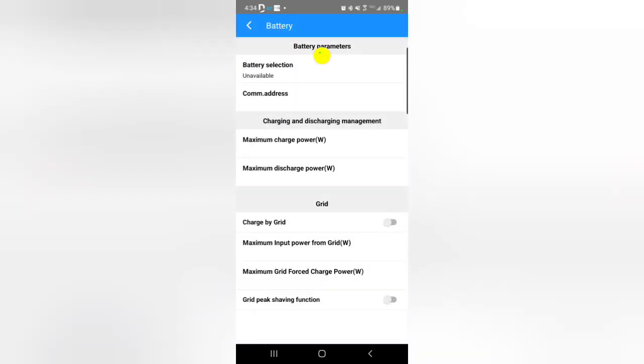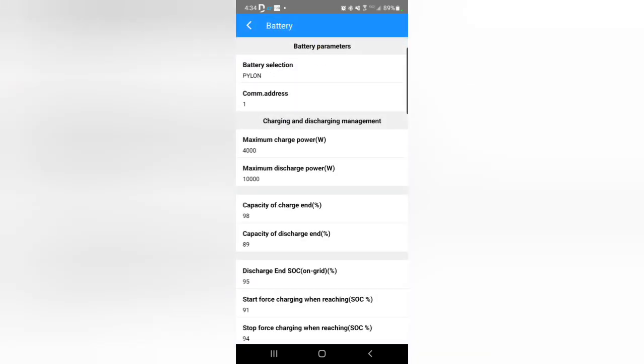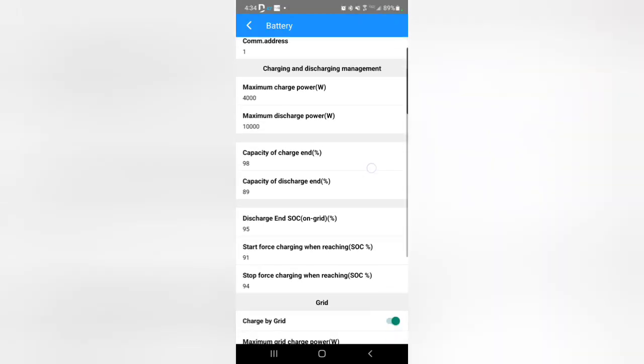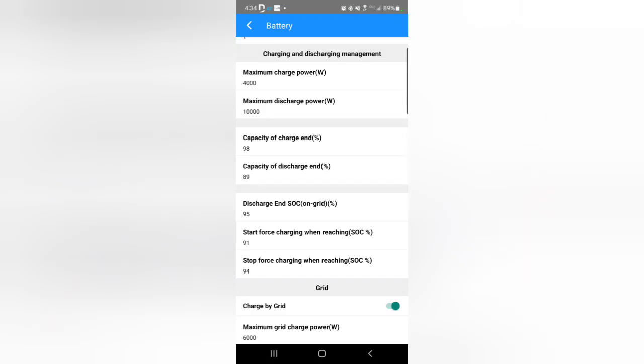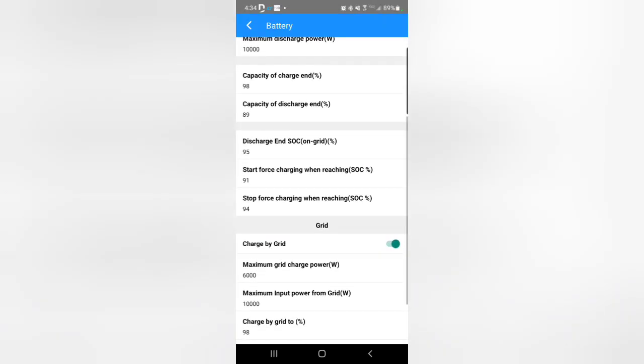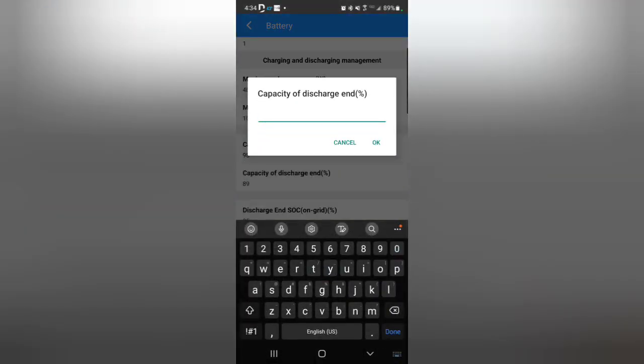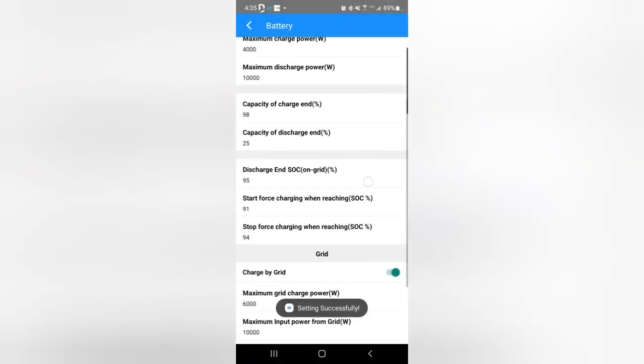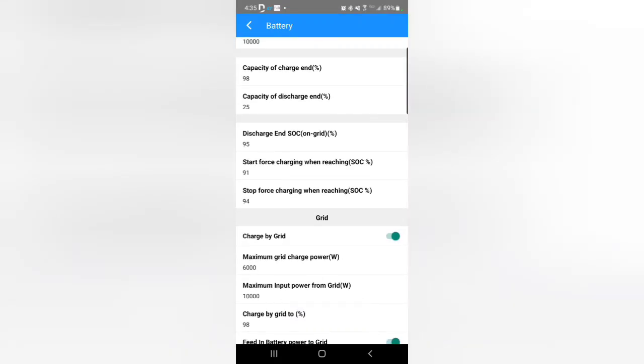Battery. If you're connected right, this will connect to your battery. You can change all these settings of how much you want to charge, discharge, capacity of charge end, 98%, discharge end 89%. Which with that discharge rate, this is when you're on grid, so I'm actually going to change that and just go like 25%. So it'll set that. So when you're on the grid, you can change those state of charge numbers. So if you want to keep it full, that's just what I'm doing, just in case there's a power failure, then we're pretty full, so it's not empty.